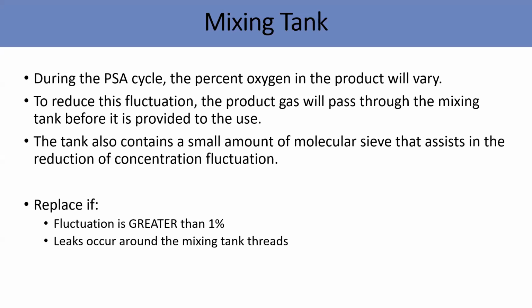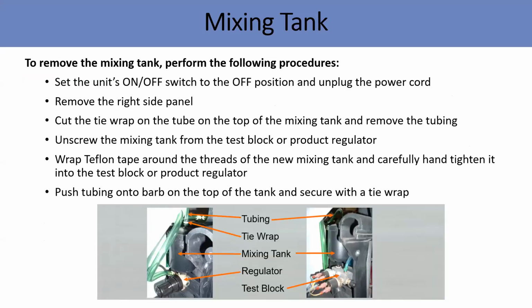Normally these are placed between the sieve tanks. For the output of oxygen, you're going to see this particular mixing tank that collects all the output that's sent through your flow. So this is where normally you're going to see the mixing tank located, near the high low pressure switch. That's the place that they normally fix it. At the same time, this is the method of removing the mixing tank, what to do, all that.